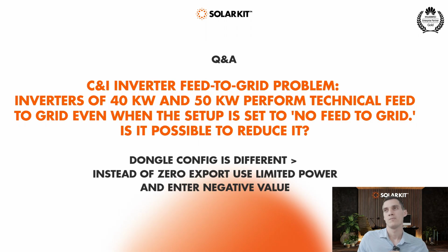And you can also start it from the bottom, like you start with negative 100 watts. But of course, in that case, until you test out the proper value, you will also feed back a little in that time period. So I would recommend to set a quite high value at first and then reduce that value every week when you see there is no injecting into the grid.